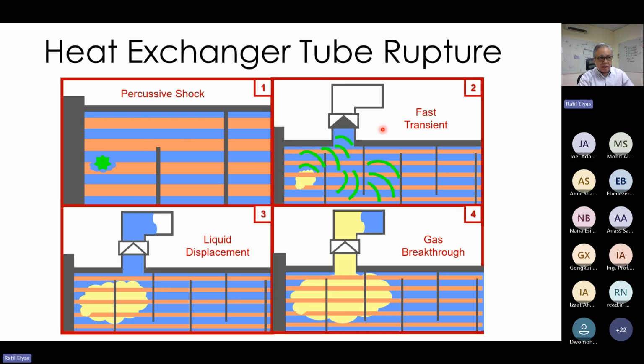The fast transient, how fast is this? Can I use a relief valve? Do I need to use a bursting disc, or can I use a buckling pin configuration? All of those have different transient responses associated with them. What kind of protection can I use? How big is it, and where do I need to place it? At the inlet, near here, or farther down? Where do I need to place this?